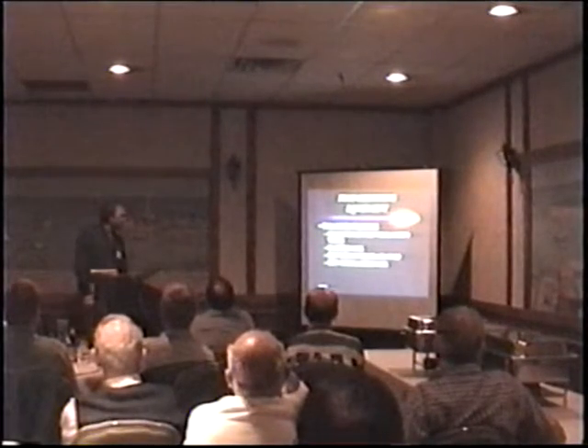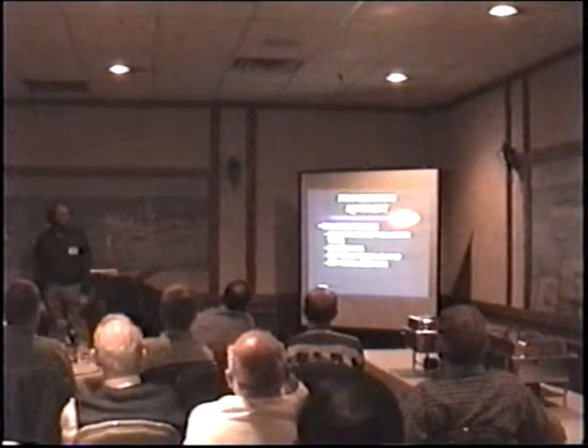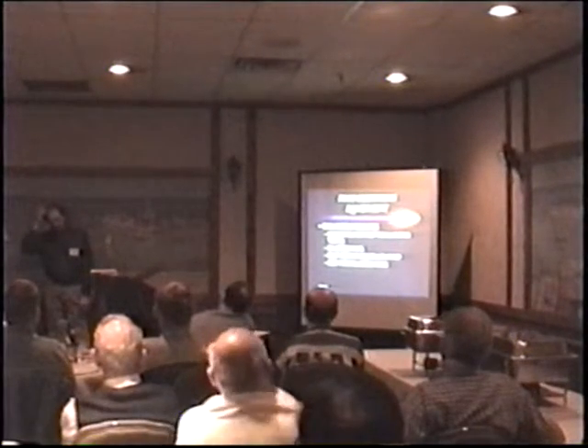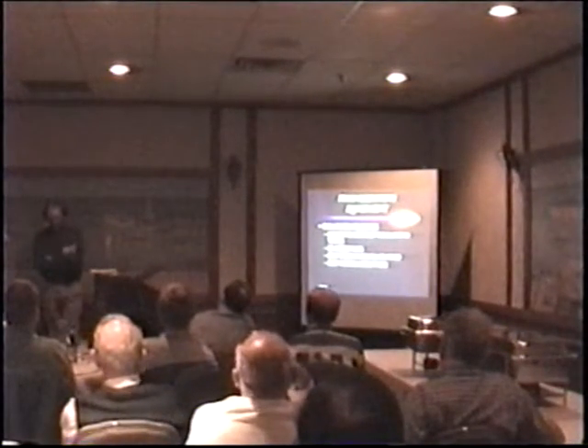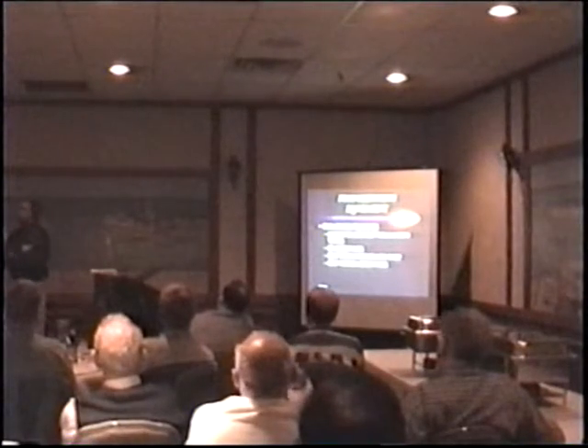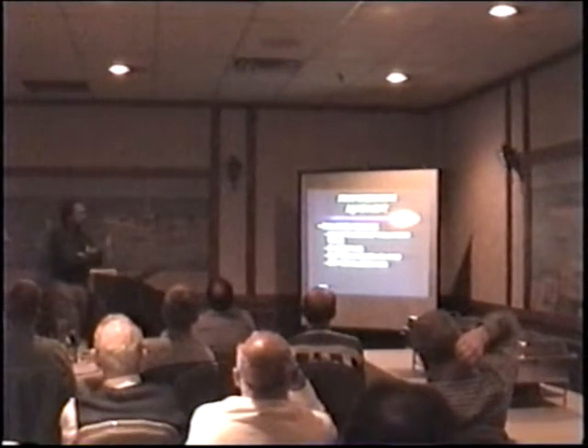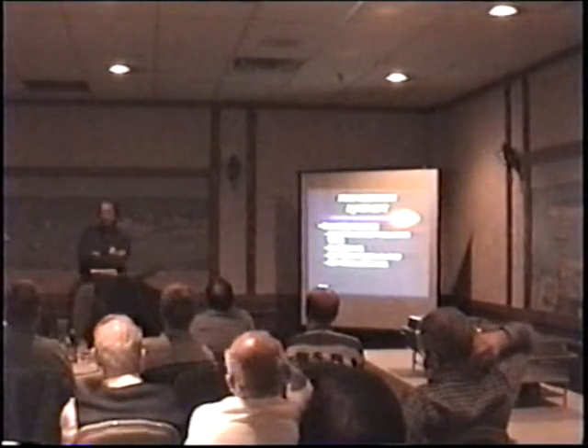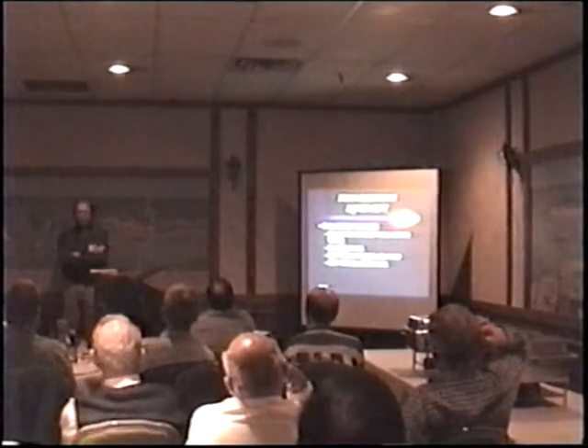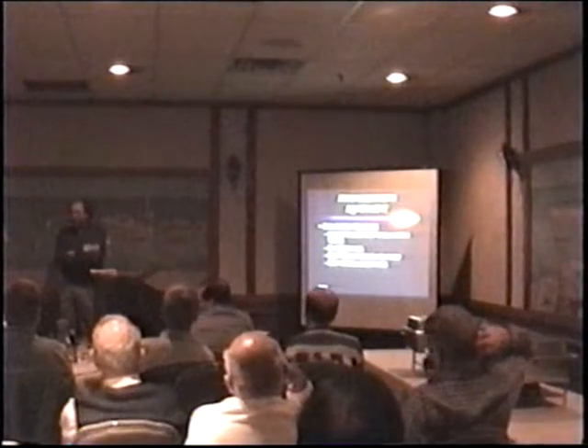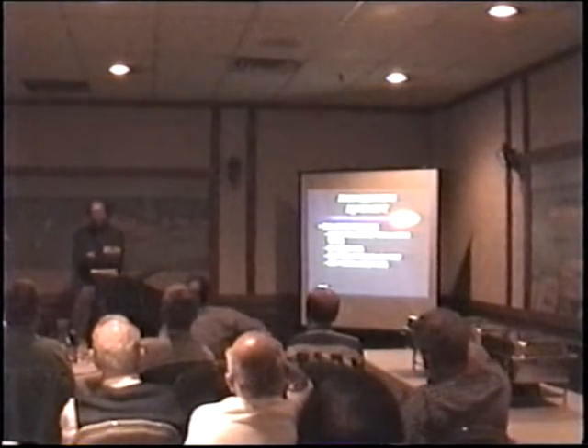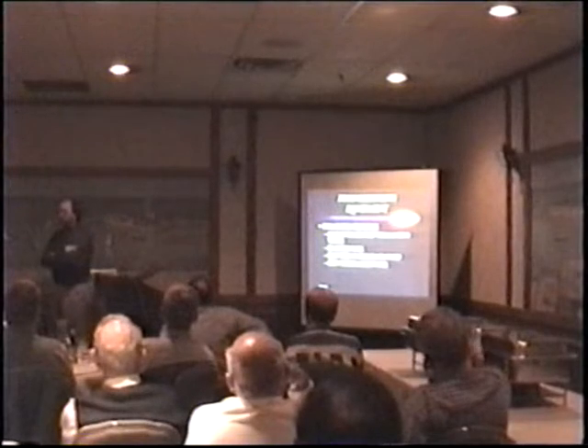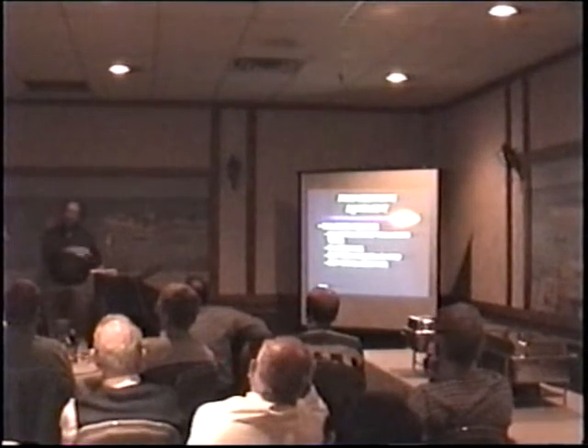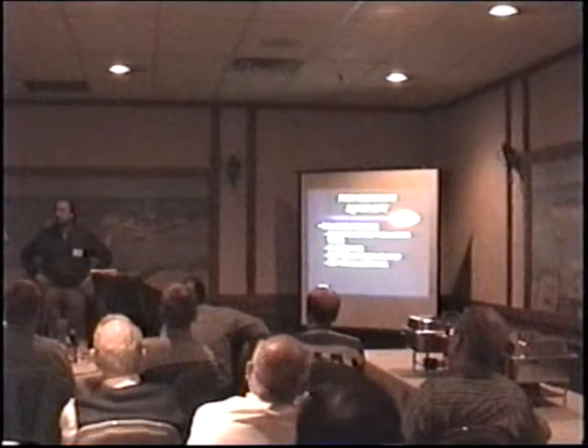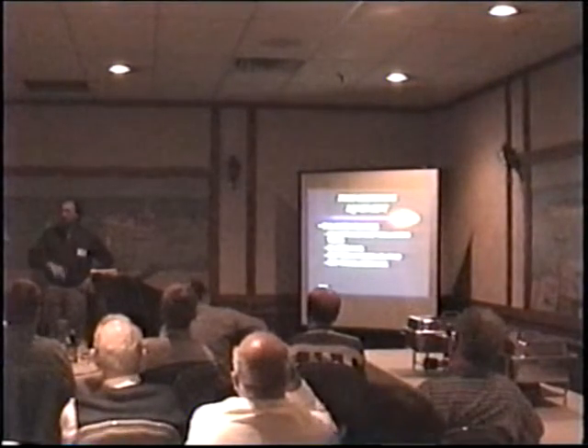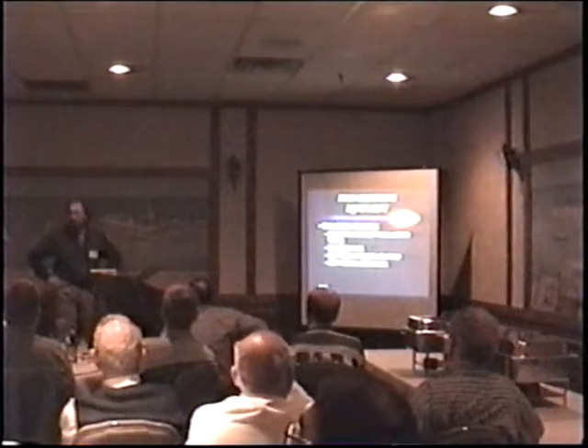The ILVP with bladder tank was developed by a company I do a lot of work with out of Michigan to kind of get some of that business away from the pump proportioner. What they basically came up with is you use the same type of ILVP, but you set it up so you put a little additional pressure on that bladder tank. It's like you're making that bladder tank into a concentrate pump. So the additional pressure on the tank gets the foam concentrate out to the balancing valve at proportionally higher pressure, where it then reduces down, balances out, and accomplishes what that pump is doing.